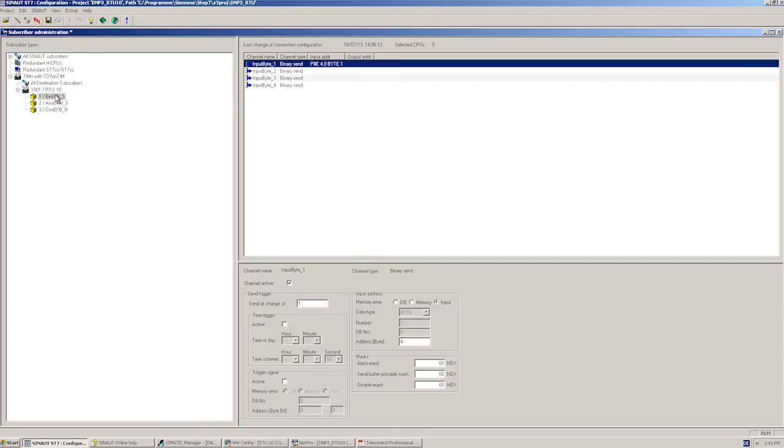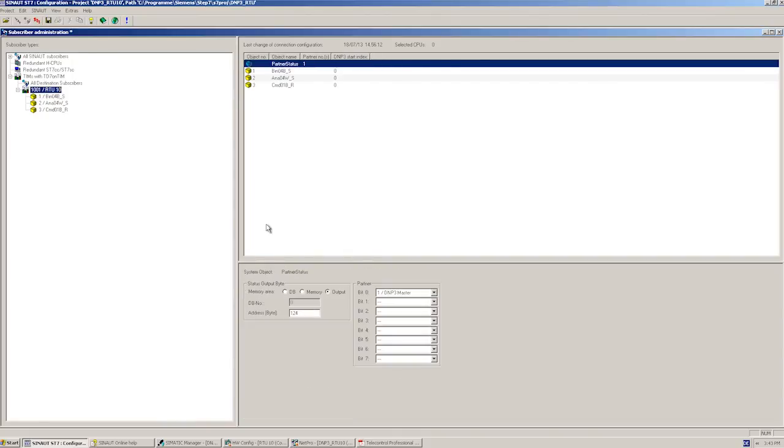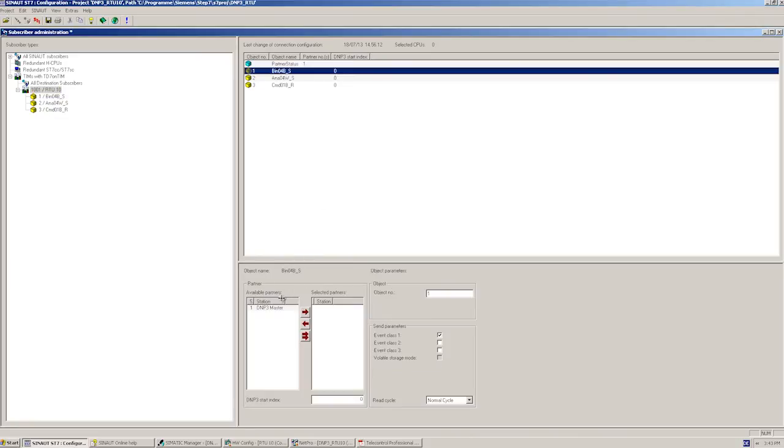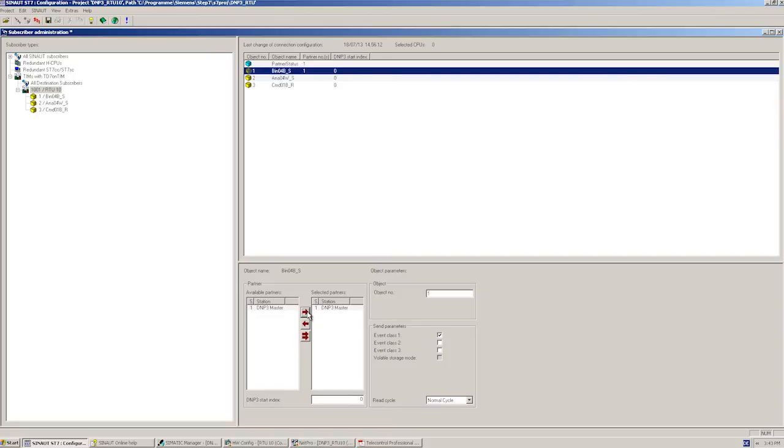Now we specify the destination station for our message, in our case the master at DNP3 address 1. Since we would like to transmit the message including the timestamp, we specify event class 1, which means the message will be event-driven and transmitted together with the timestamp to the DNP3 master. All values of class 1, 2 or 3 are called events and are transmitted both with the timestamp and with buffering.